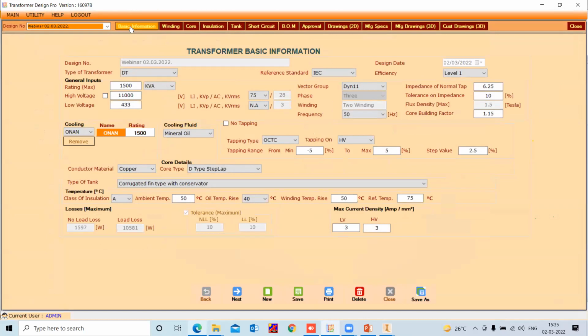Now I wish to show you one power transformer design, like 10 MVA, with another type of radiator arrangement. So let's see 10 MVA 33 by 11 kV, the dual voltage option also available. Now let's see the reference standard. All reference standards are there. Let's select the IS.